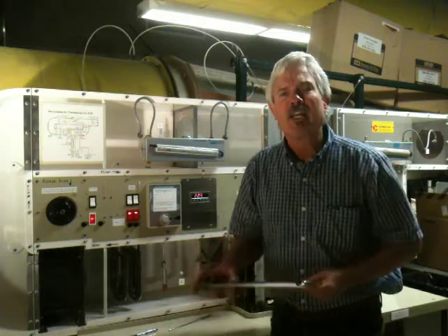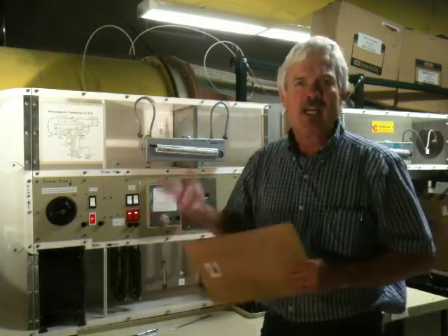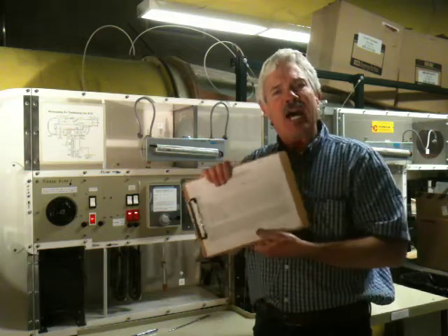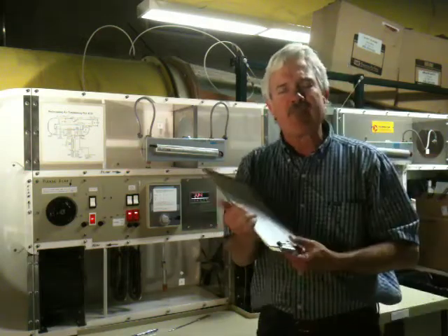All right, we've let the unit run for another extended period. So again, we've had the steam injection running, the refrigeration unit, and the reheaters. So recorded that data here. Much of it is still the same. So at the inlet A and station B, those are both relatively unchanged. C is relatively unchanged from the last couple of measurements. So again, that's immediately downstream from the steam injection.